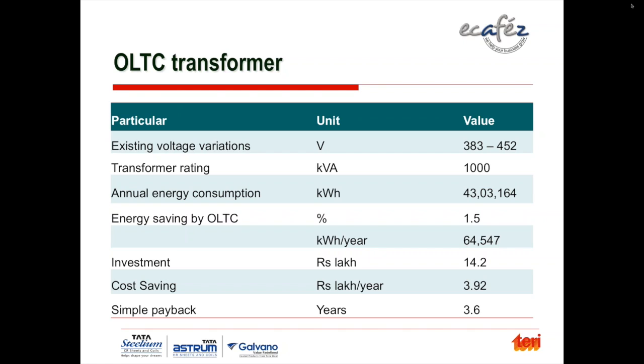Because of this, whenever the voltage is low, it puts stress on the motor, and there will be motor burnout. This was the issue. Apart from the energy saving, there was a typical issue of motor burnout in the plant. So what an on-load tap change transformer does is automatically change the tap in the transformer on load. You don't have to do it manually, so that it adjusts the output voltage to nearly what is desirable, 415 volts.